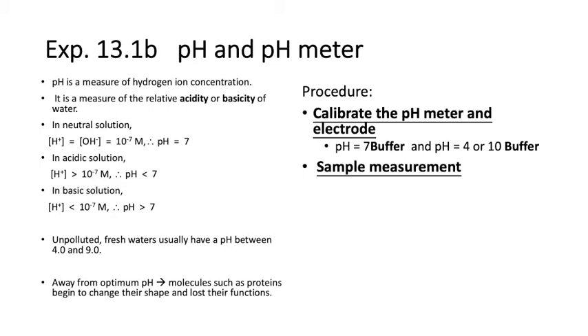For the use of pH meters, there are two main steps. The first one is the calibration. We need to conduct the calibration before the second step, measurement, if the pH meter has been idle for a long time.